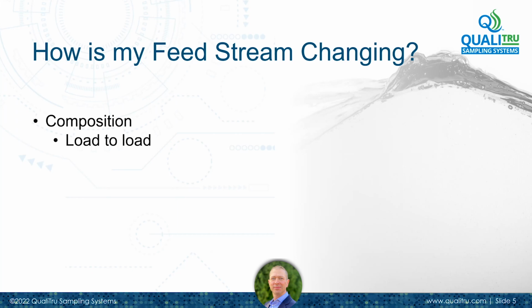Is it abrupt with reactions happening after the new stream hits? Or are there adjustments that can be made in advance that save a hit or a period of out of spec product? Can you program in the last, say, 1,000 gallons of one silo and blend it in with another? And it goes along with the expectation that some flocculation or sedimentation is going to occur over time in your suspended silos. What can you do to predict for that or make sure agitation or cooling prevents it?